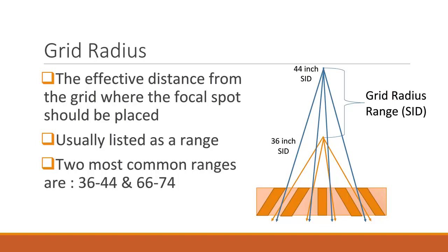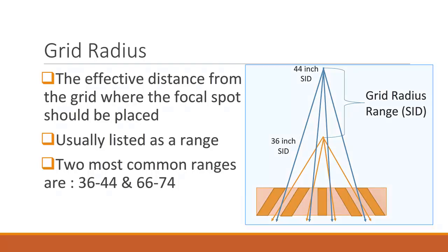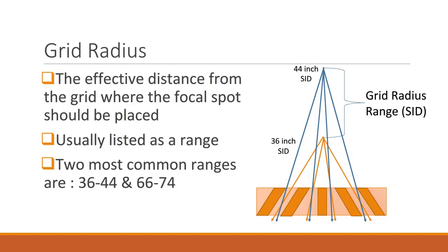Another detail often listed on the grid label is the grid radius. This is the effective distance a focused grid can be utilized. The range of SIDs are listed so the technologist knows at what source-to-image receptor distance range is feasible for the grid to be effective. The two most commonly manufactured grids are based on the two most commonly employed SIDs: 40 inches and 72 inches. In this example, we see that the grid will work at an SID range from 36 inches to 44 inches, meaning the grid radius is 36 to 44 inches.